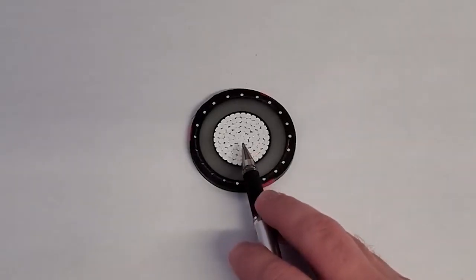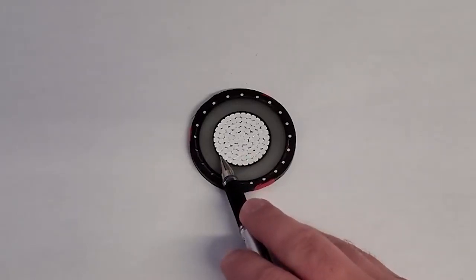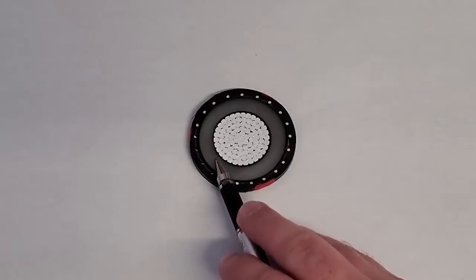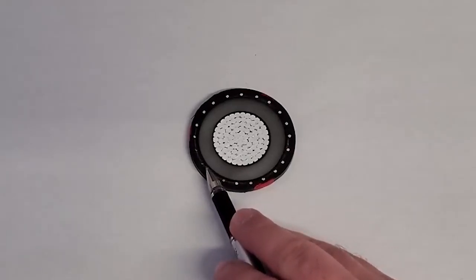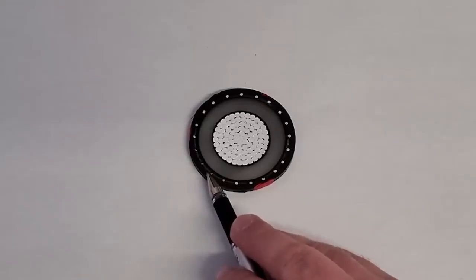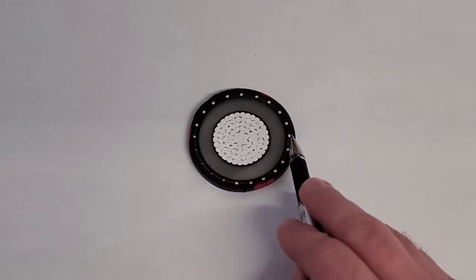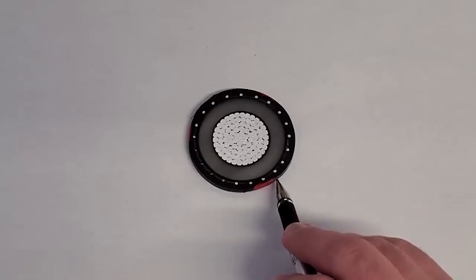The first is your conductor, which actually has your current running through it. You've got your conductor shield, this black layer. The white is your insulation. Then the black is your semicon. Then your concentric neutral layer with the copper there. And then lastly is the jacket.